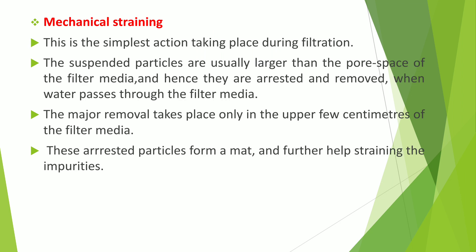First, mechanical straining. When water enters the filtration tank from the sedimentation tank, mechanical straining occurs first. This is the simplest action taking place during filtration. The suspended particles are usually larger than the pore space of the filter media, and hence they are arrested and removed when water passes through the filter media. The major removal takes place only in the upper few centimetres of the filter media. These arrested particles form a mat and further help in straining the impurities.